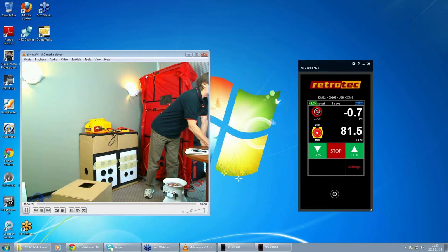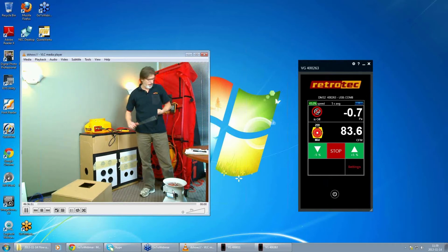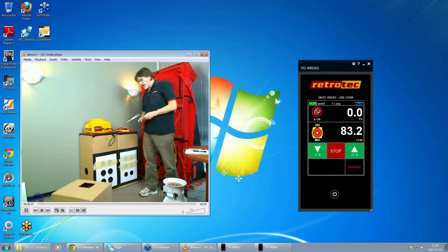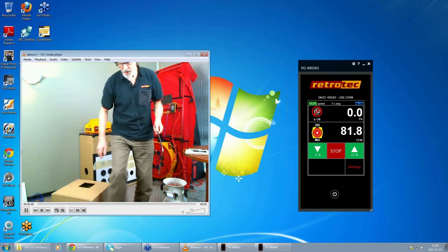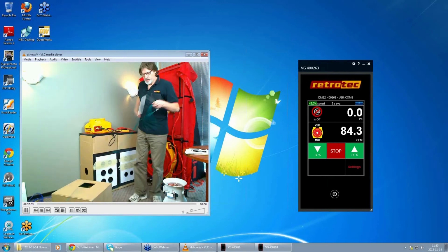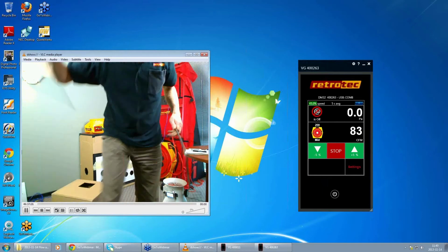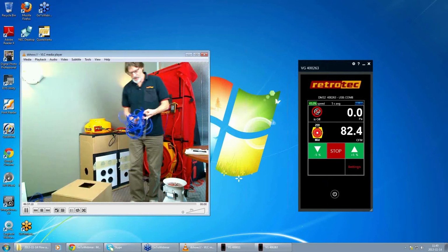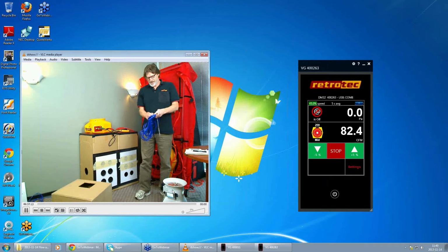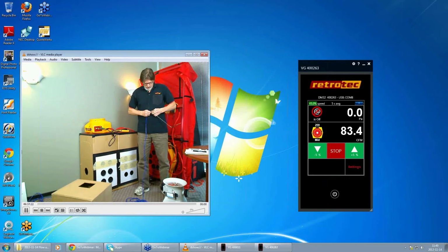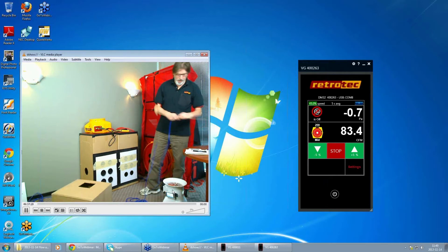So somebody was asking me again about the difference between a Pitot tube and measuring duct pressure with a static pressure probe. So a Pitot tube, which is this device here, will actually have a positive pressure. See if I can find a piece of tube here that I can stick on it. It will actually create a pressure when it's in an airstream. I don't know if I can force one of these tubes on here because it's... see if I can get one on the end here. No, I think this is way too big. Usually we put adapters on the ends of these things so we can get the tube on there. But if I was to hang this into the airstream like that, I could actually measure the velocity.